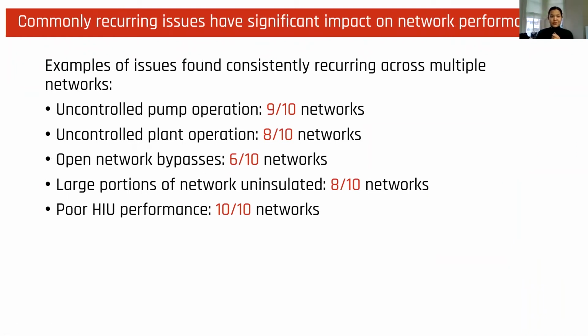So if you are a network operator and you've been sitting here thinking, what's wrong with my network? Well, this slide is for you. And based on the 10 schemes that we investigated as part of the HNOO program, we have a pretty good gauge of issues that are commonly recurring across the different networks that we took a look at. We could see that 9 out of 10 networks had an uncontrolled pump operation, which results in increased electricity consumption and cost. 8 out of 10 networks had an uncontrolled plant operation, which results in decreased generation efficiency.